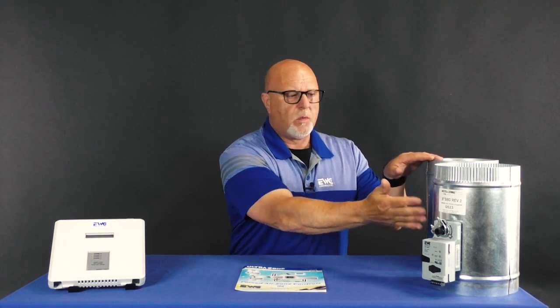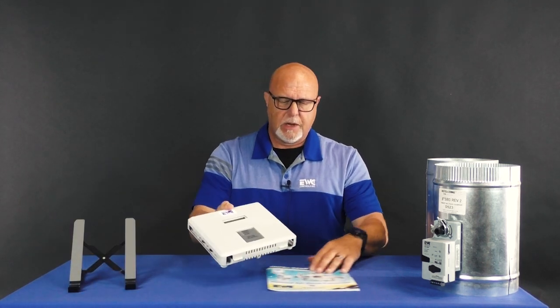Now, in the event that you go to a job site and determine that the system you are looking at and the homeowner wants zoning, but there's just not enough room to put one of these and the associated ductwork that must be installed for it. If there's not enough room for that, historically, you would probably walk away from that job because the system needed that bypass, that ability to handle that excess capacity. And in those situations, like I said, you would walk away. And in the summer of 2023, EWC introduced the DAPC.